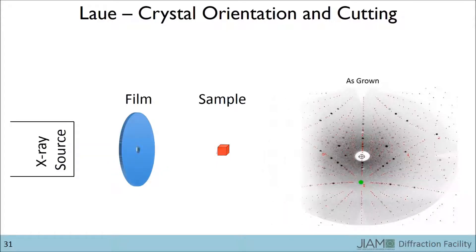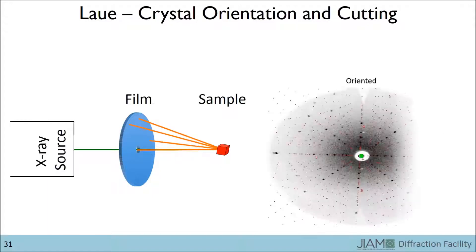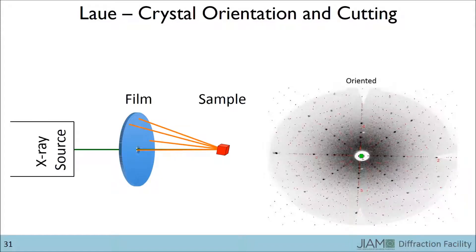Using our goniometers, I rotated the sample, ran another test, and found that the 1-0-0 plane was now in the center of the pattern, which means that it is perpendicular to the X-ray beam.